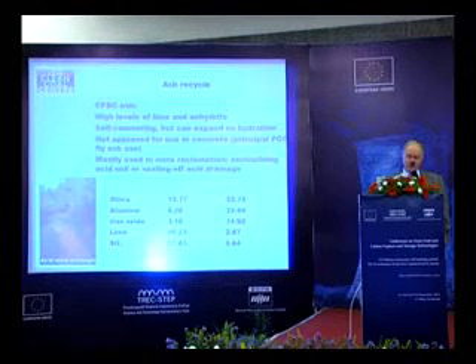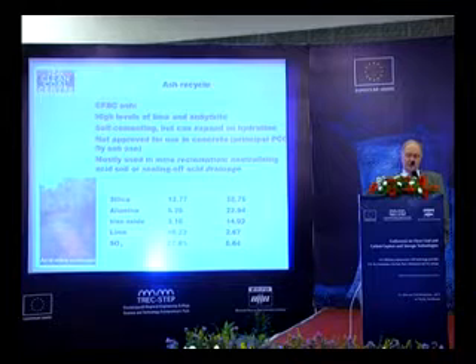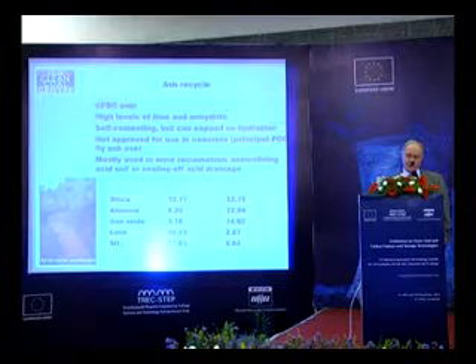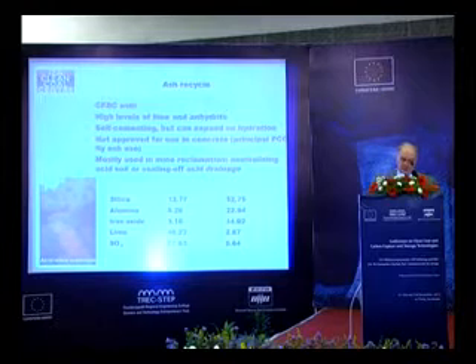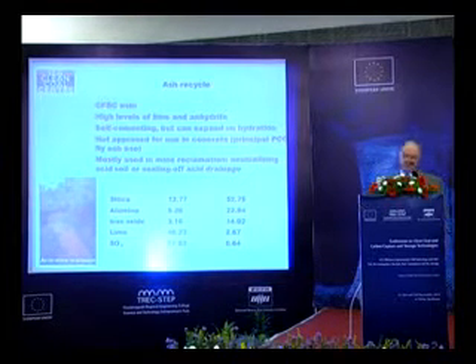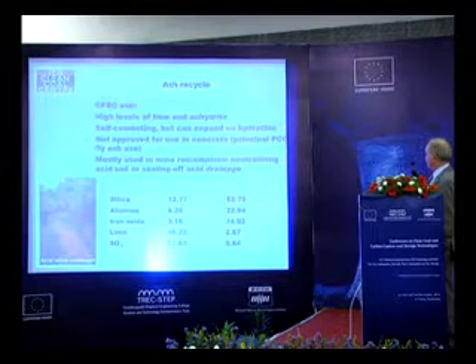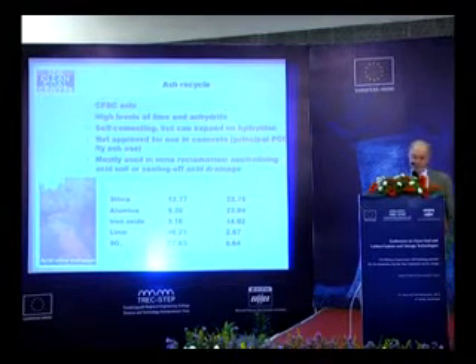On ash, CFBC has a disadvantage compared with pulverized coal. You get high levels of lime and anhydrite in CFBC ash; it tends to be self-cementing and is not approved in most jurisdictions for use in concrete. A lot of PCC ash gets used that way, but not CFBC ash. CFBC ash tends to get used in lower-grade construction applications, neutralizing acid soils, or sealing off acid drainage. The ash specifications are quite different — silica content varies significantly between PCC ash and CFBC ash.